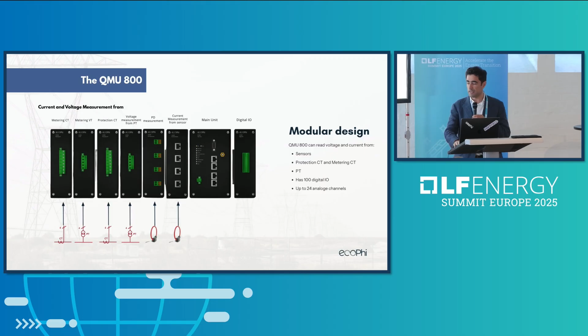A bit more on the merging unit: it can connect to all types of sensors. If you want conventional CT/VT, you use a CT/VT card. If you want low-power CTs or Rogowski coils, you can use a Rogowski coil. We can monitor PD, and other applications like power quality monitoring can be deployed in it as well.